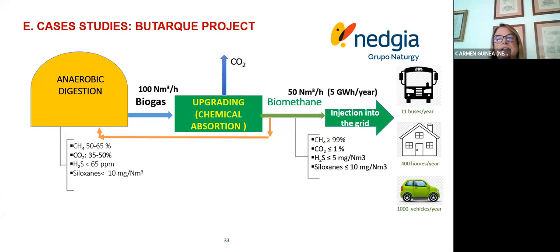This plant has 3 digesters, each one of 10,000 cubic meters. From them, the upgrading receives 100 cubic meters per hour of biogas and produces around 50 cubic meters per hour of biomethane for injecting into the grid. This is 9% of the total biogas produced in the wastewater treatment plant. 90% of the biogas is sent to 3 cogeneration motors, each one around 1 megawatt, that produce energy for the wastewater treatment plant consumers. This upgrading plant produces enough energy to feed 11 buses or 400 homes or 1,000 vehicles per year. That is 5 gigawatt hours per year of energy.